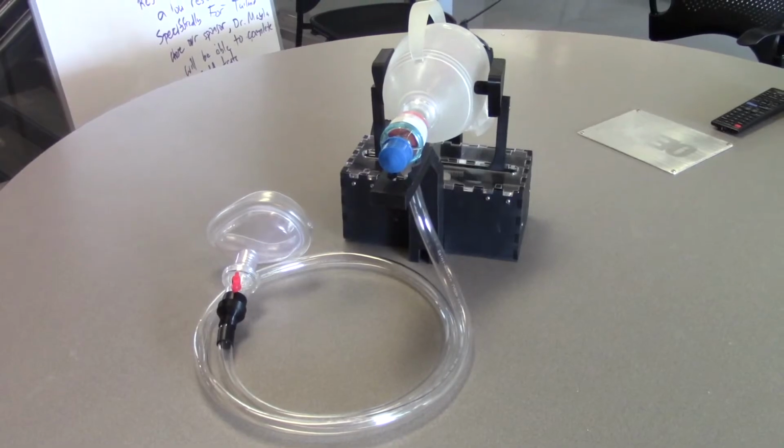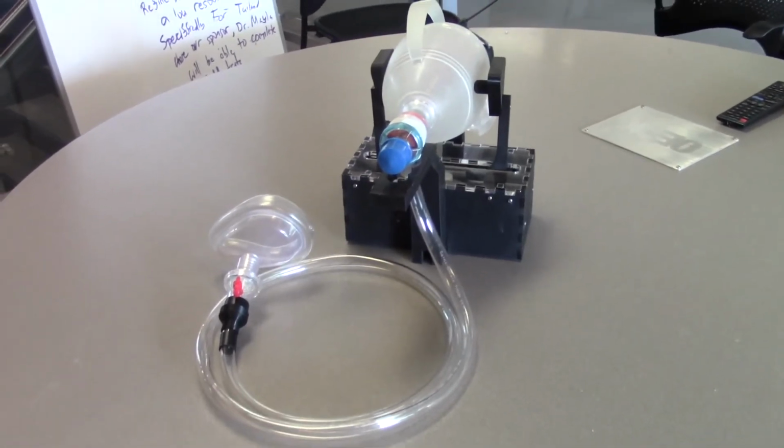When designing the device, there were several criteria we had to consider. First, we wanted it to be low cost, since this is for low resource settings. We also wanted good control of the breaths per minute and the volume provided, so that we can provide sufficient ventilation. We also wanted to limit size and weight of the device so that it can be portable. Additionally, the device needs to last for a long time, so it can be a proper replacement for the ventilator. And finally, we wanted to limit power usage, since these are low resource settings and power may not always be available. So this is our device, the automated bag valve mask.